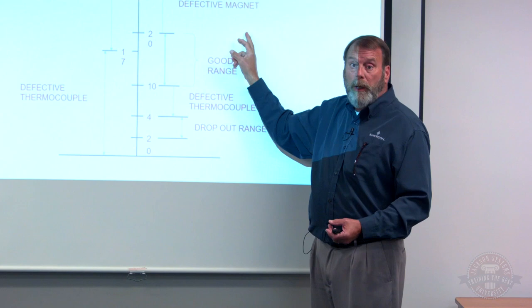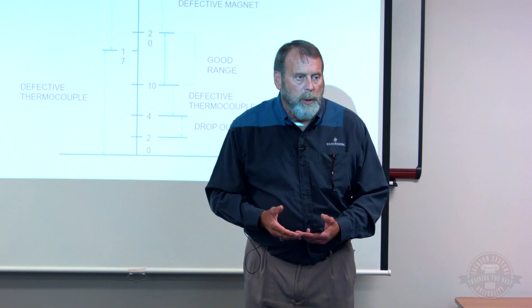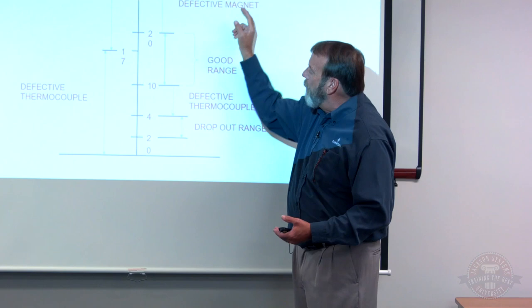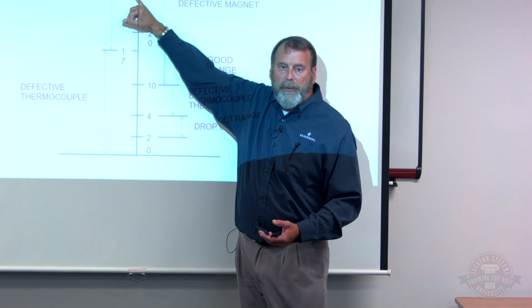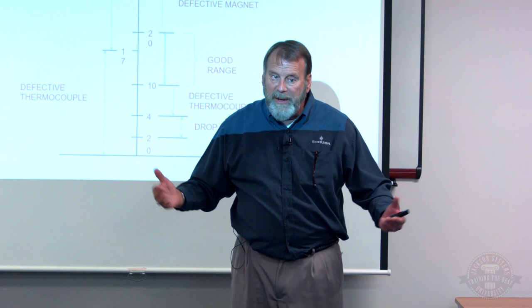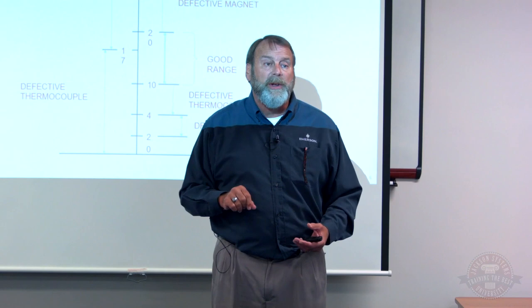Typically on a gas valve, you'll see two little 3/16 spades right where the thermocouple gets screwed in. Normally an ECO, an emergency cutoff or energy cutoff switch, a thermal fuse, is tied to that. You can actually measure it under load here. As an open circuit, when it's just hanging up in the wind, 17 millivolts is the bottom threshold. With no load, it'll be somewhere between 17 and 30 millivolts. If you're getting that, it's putting out enough voltage to hold the magnet in. You don't have a bad thermocouple. If it's down in this range down here, it's not putting out enough voltage. It could be either A, the pilot burner is not producing enough heat, you don't have it immersed about 3/8 of an inch into the flame, or your thermocouple is becoming defective.